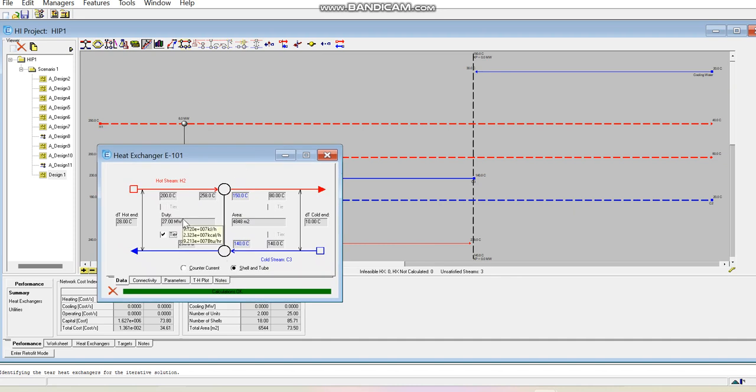that means that if the cold achieves its target temperature 230, it has to take 27 megawatt. How to take 27 megawatt? The hot stream must enter at 258 degrees C. But the hot stream is available at 200 degrees C. So that means that this hot stream is not enough to heat this cold stream to its desired point.